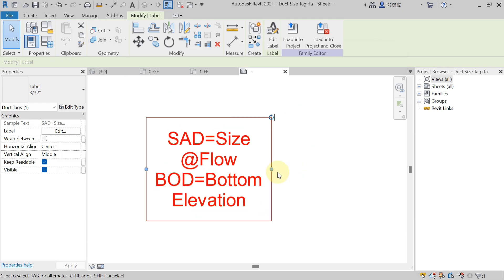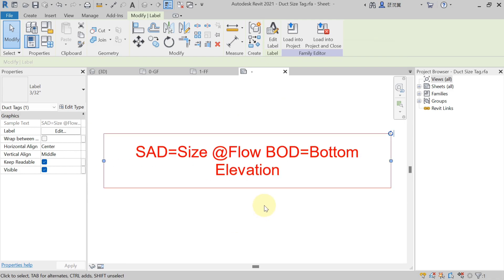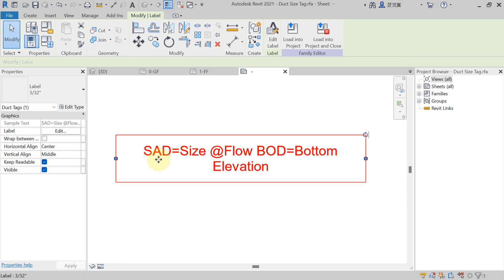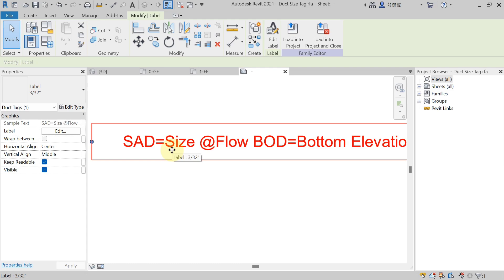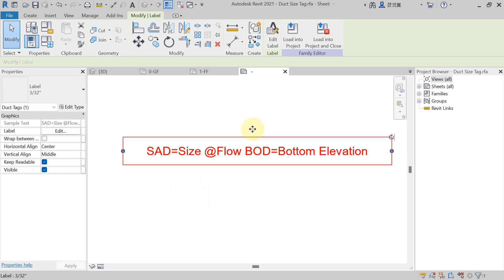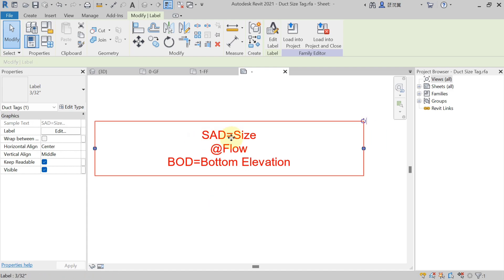If you have not checked Break and hit Apply, the problem is that in the tagging all values appear in a series on one line — first the duct size, then the flow value, then the bottom elevation. But if you want the size on the first line, flow value below it, and bottom elevation below that, go to Edit Label, check the Break checkbox, then hit Apply. Now in the tagging you will get the size first, then the flow value below it, then the bottom elevation below that.